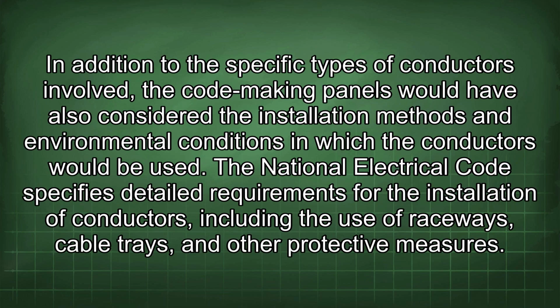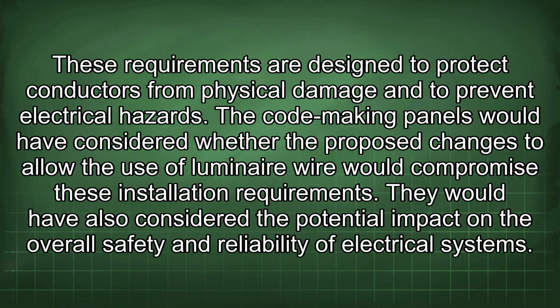In addition to the specific types of conductors involved, the code-making panels would have also considered the installation methods and environmental conditions in which the conductors would be used. The National Electrical Code specifies detailed requirements for the installation of conductors, including the use of raceways, cable trays, and other protective measures. These requirements are designed to protect conductors from physical damage and to prevent electrical hazards. The code-making panels would have considered whether the proposed changes to allow the use of luminaire wire would compromise these installation requirements. They would have also considered the potential impact on the overall safety and reliability of electrical systems.